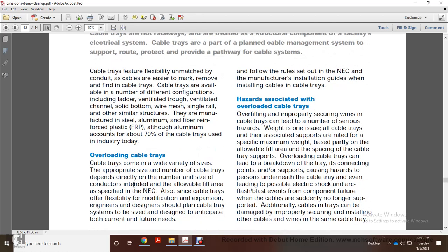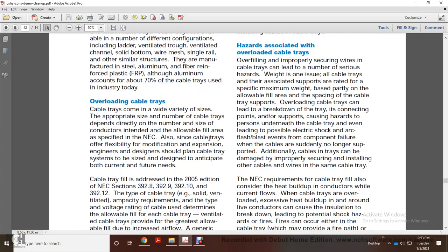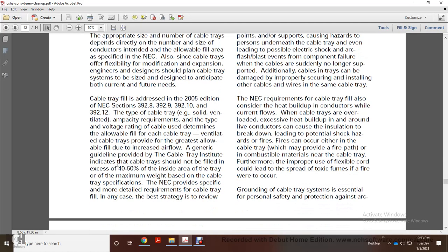Overloading cable tray. Cable trays come in a wide variety of sizes depending on the number and size of the conductors intended to be carried, as associated with the National Electrical Code. Also, since cable trays are flexible for modification and expansion, engineers and designers should plan the cable tray system size to anticipate both future needs. Cable tray fill is addressed in the 2005 National Electrical Code edition, Sections 392.8, 9, 10, and 12. The type of cable tray, solid or ventilated, the ampacity requirement, and the voltage rating of the cable are used to determine the allowable fill of each cable tray.